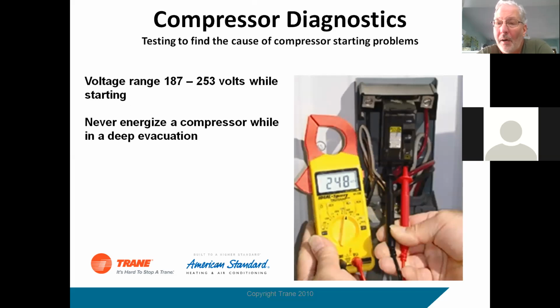Okay, so we have to look at wires. We have to look at different things in the system to see what's going on with the compressor or the wiring to the compressor. The other side that you have to be aware of is the high voltage. So make sure that we're not exceeding 253 volts while starting. The windings and the insulation on a lot of the components aren't going to take that high voltage, and it's going to shorten the life of the compressor, shorten the life of the contactors, the boards.